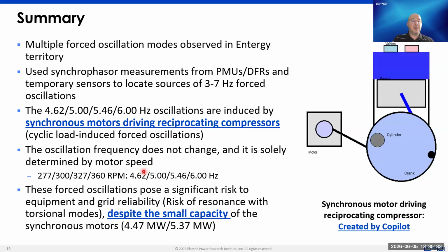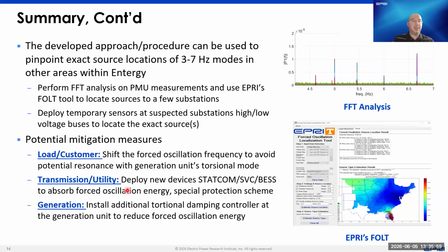Again, the reason for the investigation is to investigate whether there is a risk of resonance between those oscillations and the torsional modes of generators in different areas within the system. In terms of the analysis, as I said, we used simple conventional FFT to observe the oscillations and the modes in the PMU data sets that we used. And we also used EPRI's forced oscillation localization tool to support the analysis and pinpoint the source.